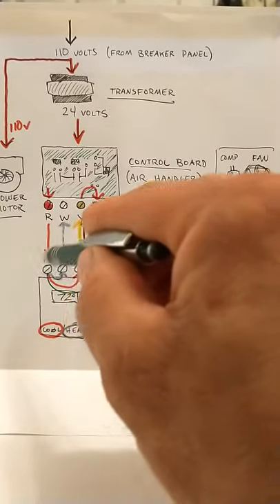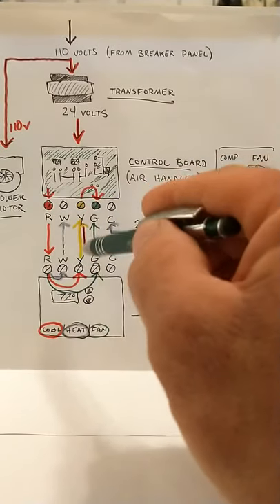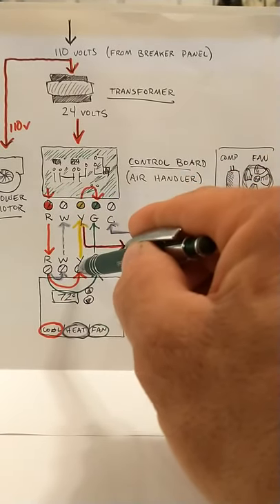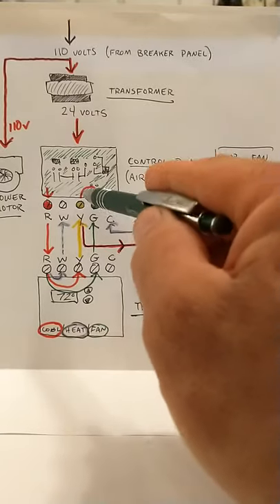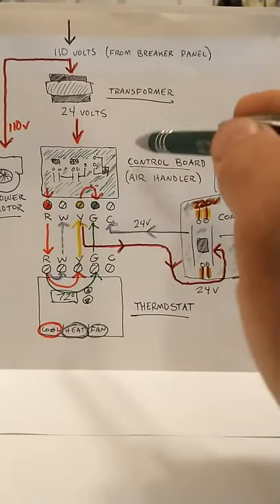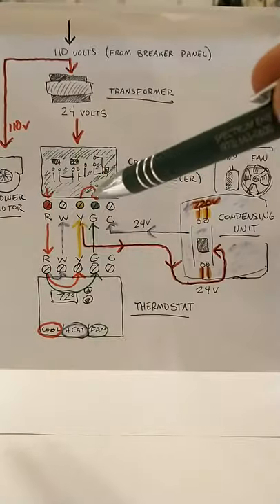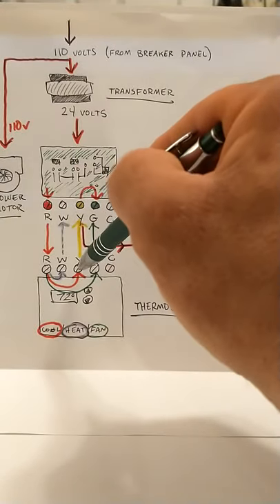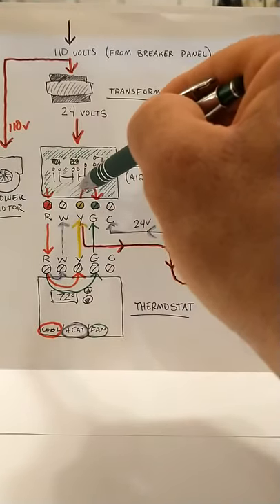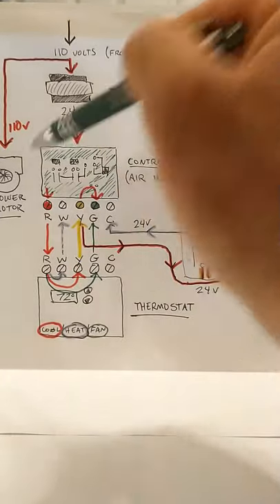When that circuit's closed in cooling mode, your 24 volts will travel from your Y in your thermostat to the Y terminal at your air handler. And what that does is it signals the blower motor to kick in. So your 24 volts will travel through that wire. Once it's registered here, your fan will kick in. The blower motor will kick on.